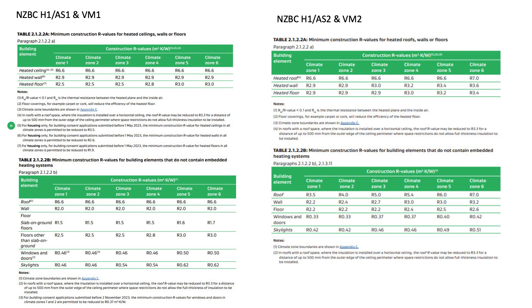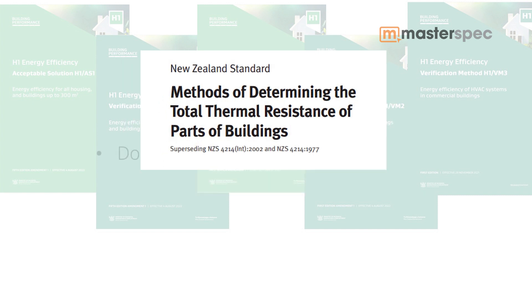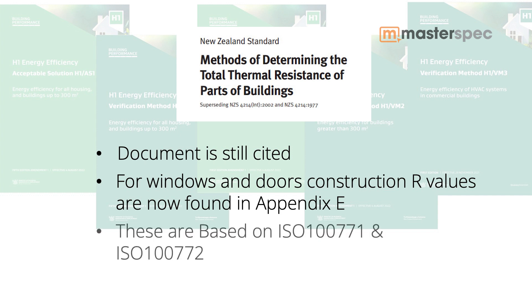Those R values have all gone up across the board. It's also worth mentioning that the existing H1 documents referred to NZS 4214, which is the methods for determining total thermal resistance of building parts. This document is still cited — it's used to determine the thermal resistance of walls, roofs, opaque doors and slabs other than slab on ground. But for windows and doors, construction R values are now found in Appendix E. These are based on ISO documents — ISO 10077-1 and 2 — and for glazing, BS 673.